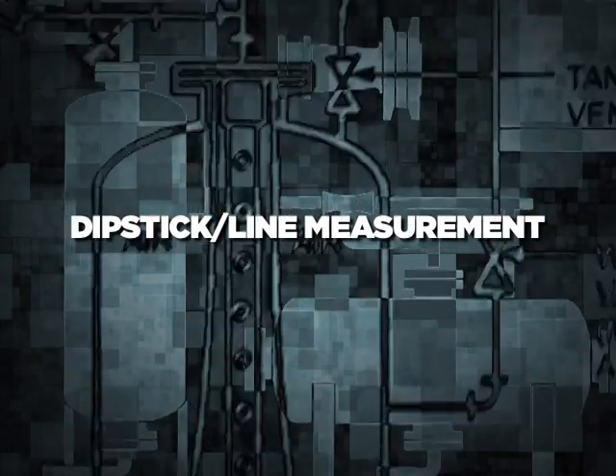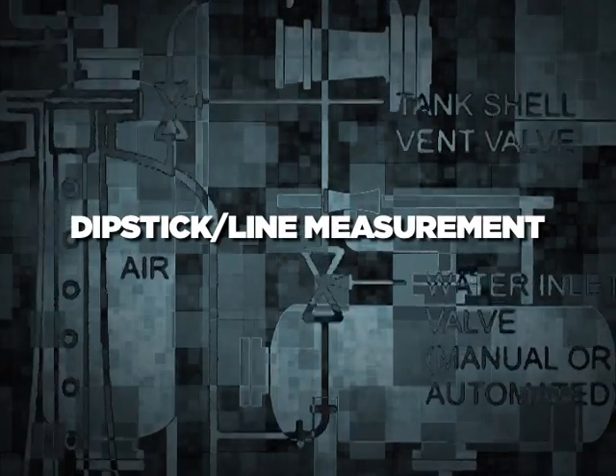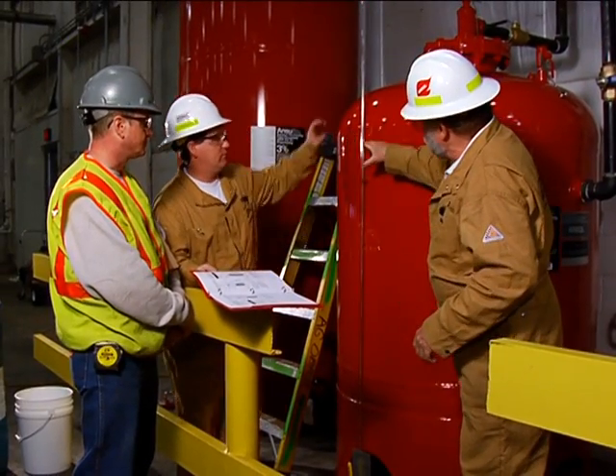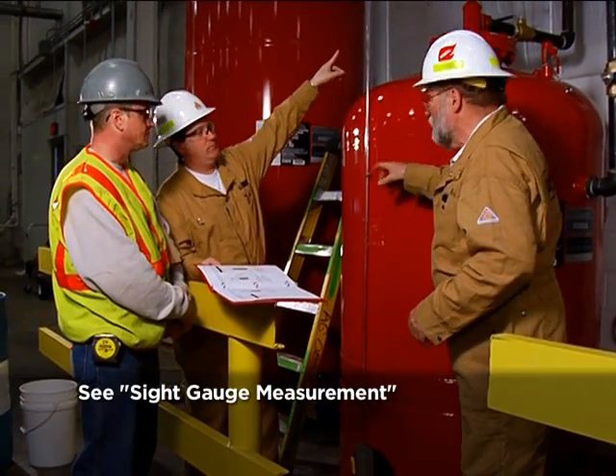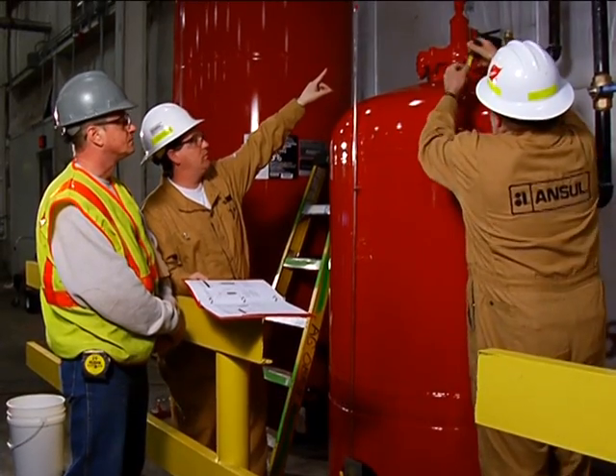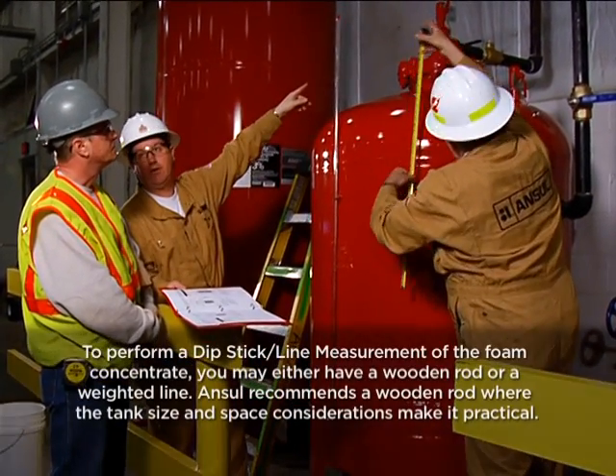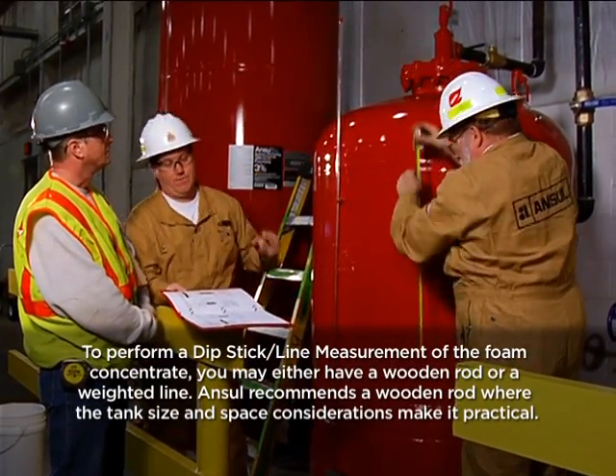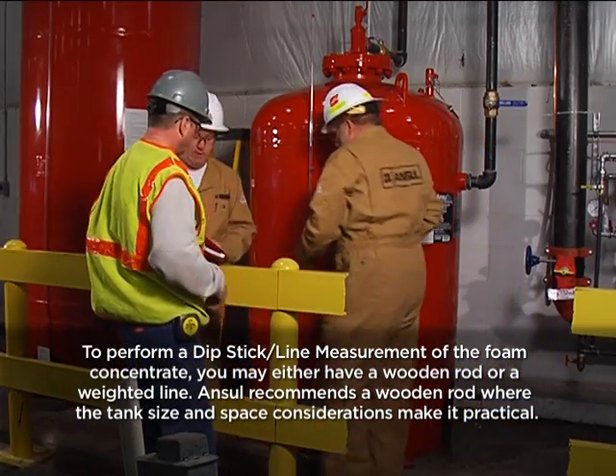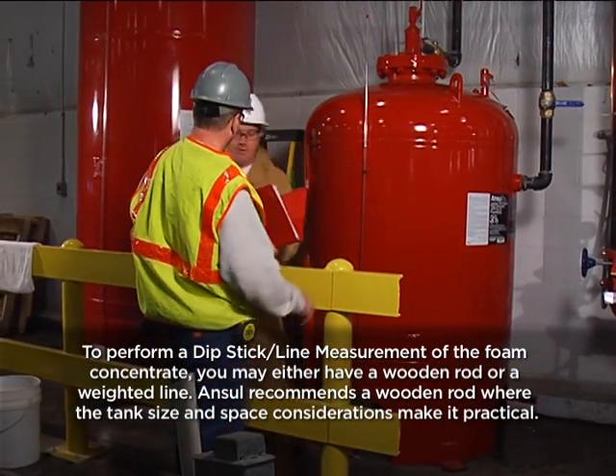Foam concentrate measurement procedures using a dipstick line measurement. There's actually two methods that can be used. You can use the liquid level gauge, and another way of doing it is you can run a tape measure down the center, through the top of the tank. I'll demonstrate that.